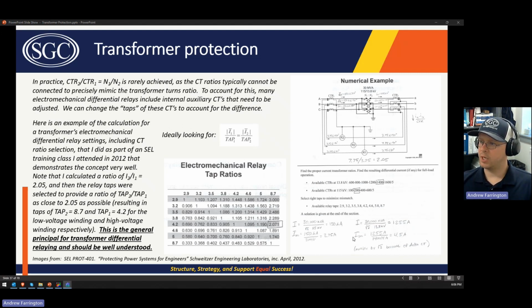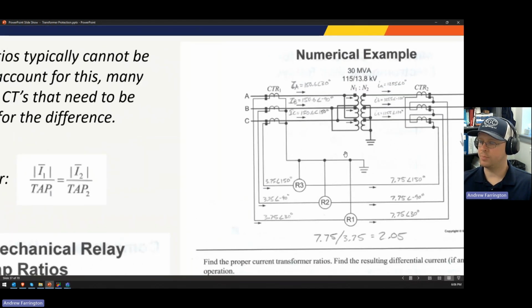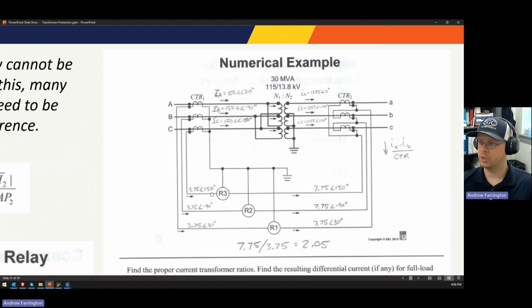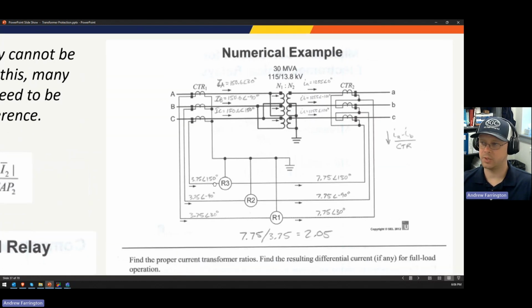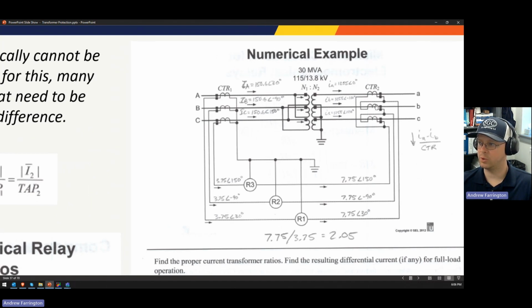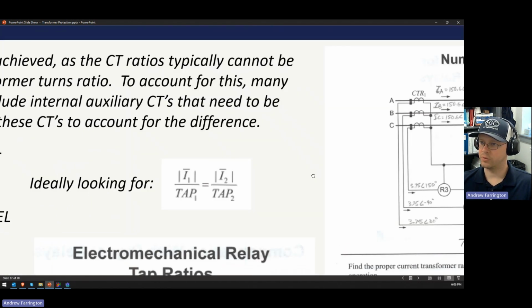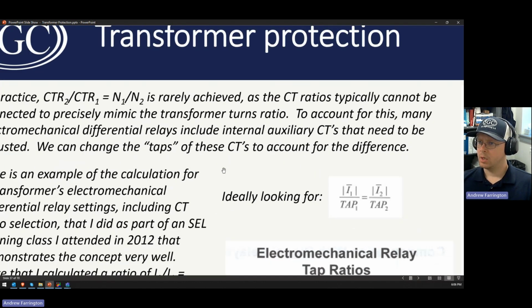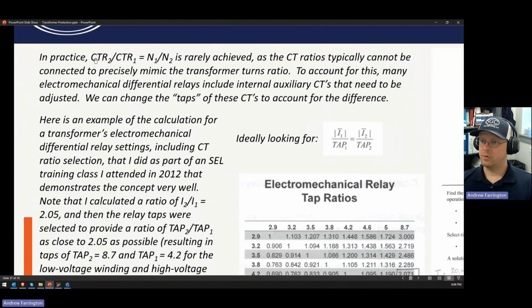So this was from a Schweitzer protection class I did a dozen years ago or so. And we're going to walk through this example, and this will be very similar to one of your homework problems. So rely on this to go back and recreate what the homework problem is. Like I said, in practice, your ideal CT ratio is not going to actually match the turns ratio of the transformer. So you've got different taps that you can use.